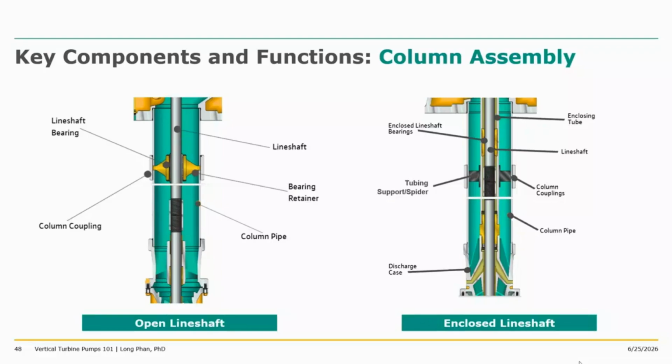And then on the enclosed line shaft, since you have an extra tube assembly that the shaft is enclosed fully inside, you will have some mechanism to support these tubes, to support spiders, and then enclosed line shaft bearing.